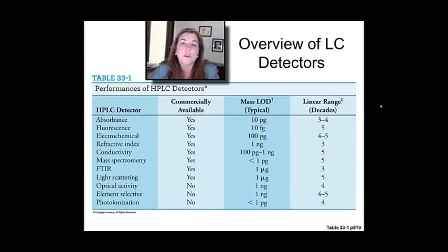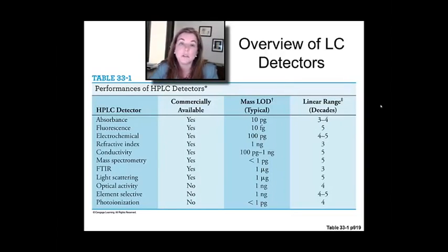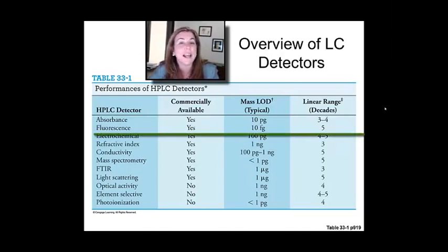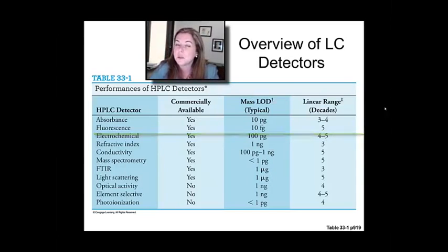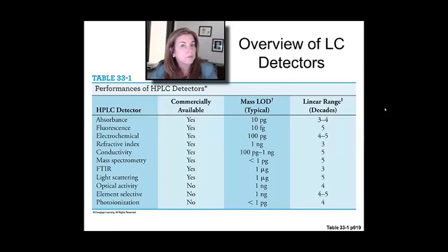Here's an overview of LC detectors — all the ones that you can buy. You'll notice in your reading examples of fluorescence detectors. Those can be extremely sensitive; fluorescence can get you down to femtogram levels if you're lucky enough to have an analyte that has a good fluorescence yield. Absorbance is kind of on the picogram scale. Refractive index is at the nanogram level, so pretty functionally different detection limits.